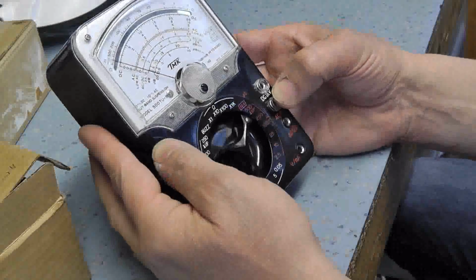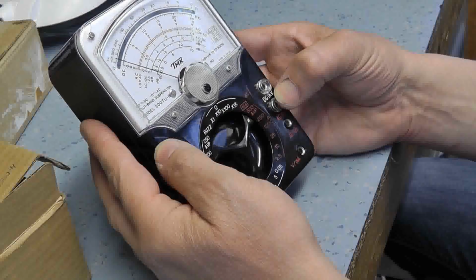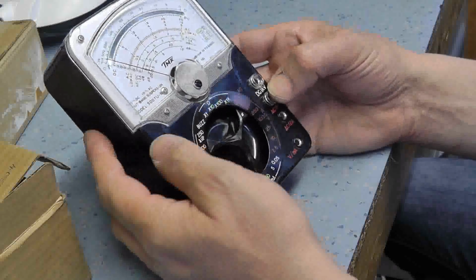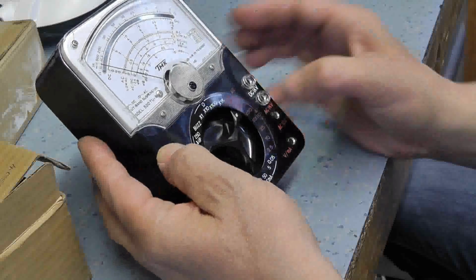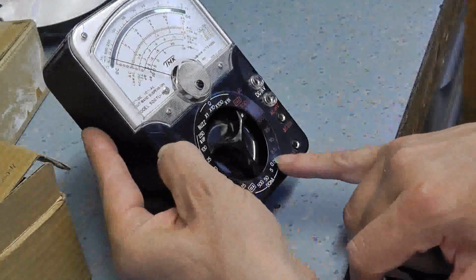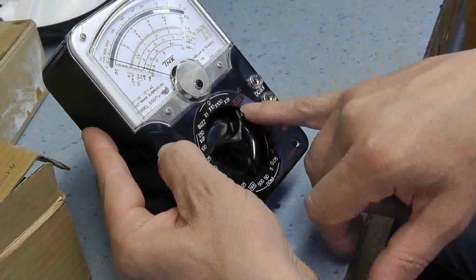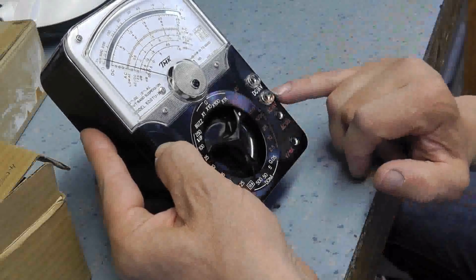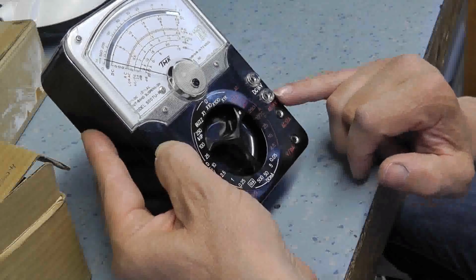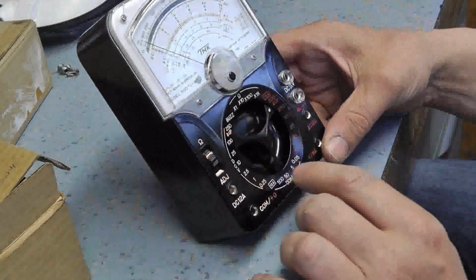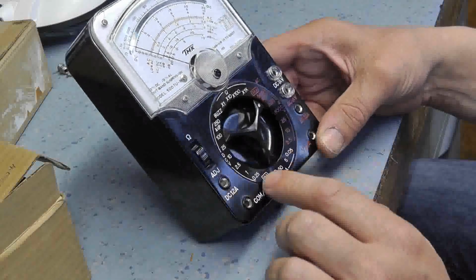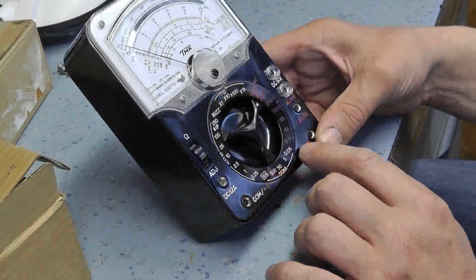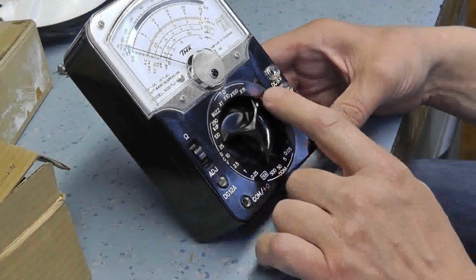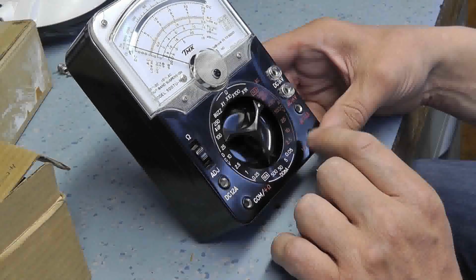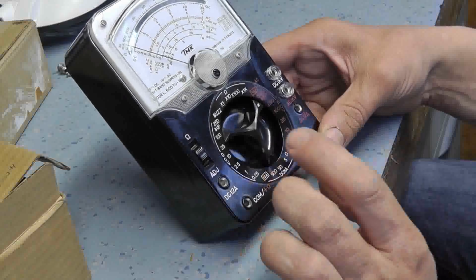So it's a 20,000 ohm per volt range on DC, and I think it's 10,000 on AC. You've got various ranges from 2.5 volts AC up to 500 volts, and 1 kV with its own dedicated connection. We've got amps up to 12 amps DC, which is nice, but we've also got up to 12 amps AC as well, which is also good, because it's actually got a current transformer built in.